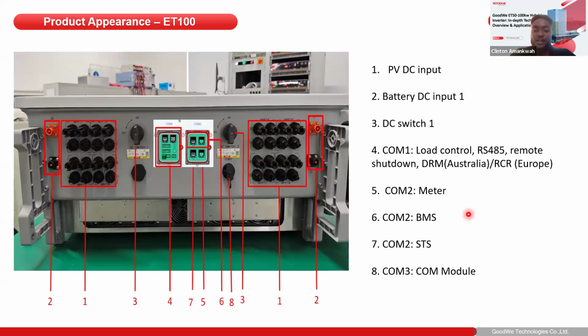Now, aside from the introduction of the LCD screen, we also have multiple MPPTs and dual DC battery input slots. So from the 150% DC oversizing of the ET50, we have now achieved 200% DC oversizing on the ET100. We came up with this by having 8 different MPPT inputs, each with two strings per MPPT, and then 42 amp DC input current per MPPT. So you have 8 different MPPTs here, 2 slots per MPPT, giving you 16 slots in total.